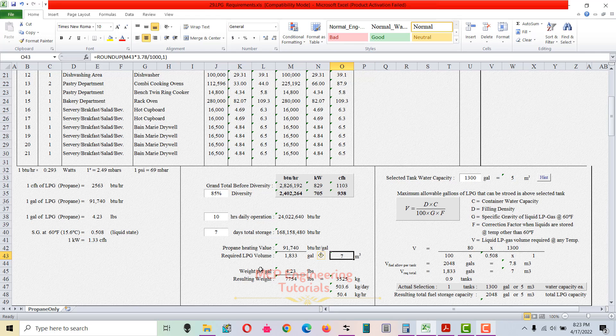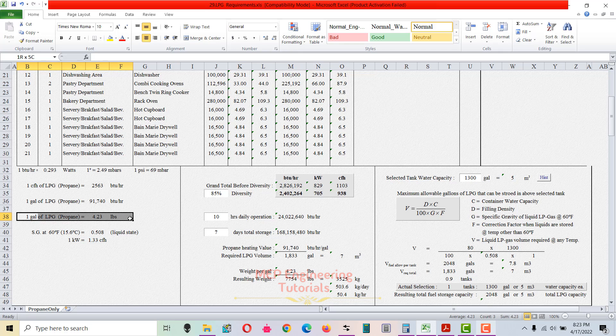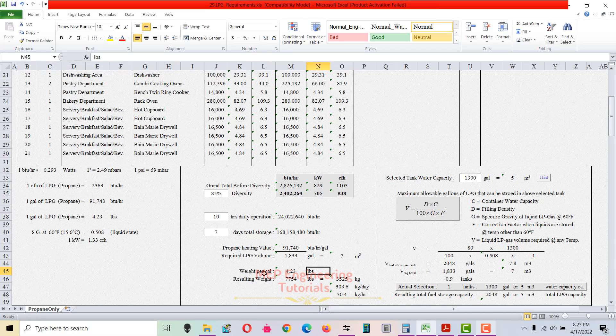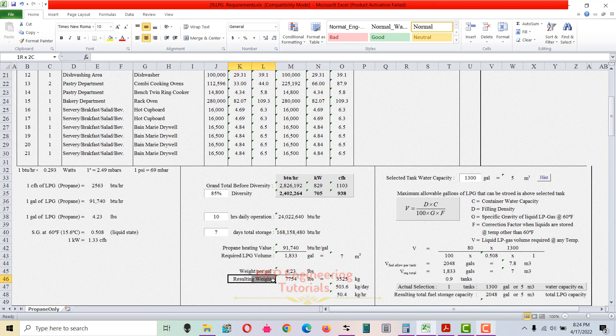Now calculate the weight of LPG to be stored. One gallon of LPG propane weighs 4.23 lbs — remember, this value applies to 100% propane; if you have a mixture, this value changes. Multiplying 1,833 gallons by 4.23 gives a total weight of 7,754 lbs, which equals 3,525 kg.